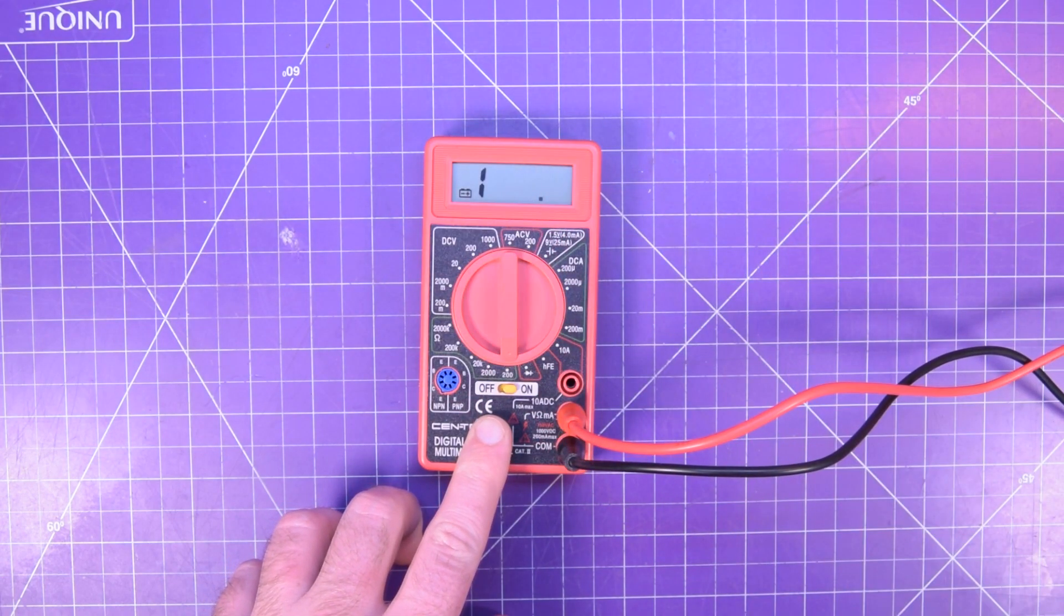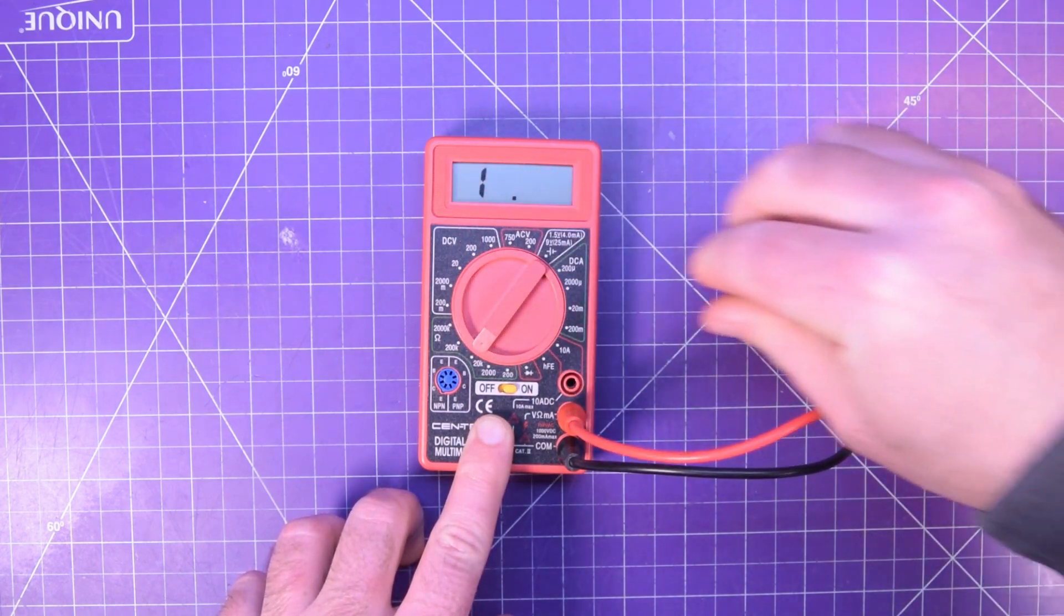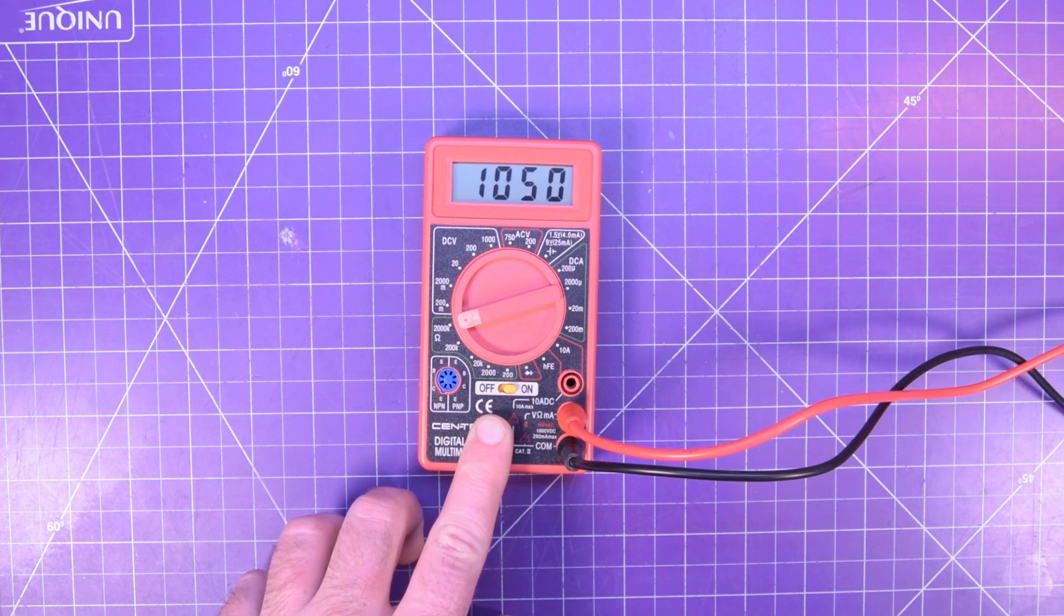Just select the range that is higher than what you expect to see. If you have no idea what to expect, just start at either end of the range while testing and work your way to the other end until you get a concrete measurement. As with continuity, your circuit must be isolated or disconnected from power before you test for resistance. Ideally, you would remove it from the circuit altogether.